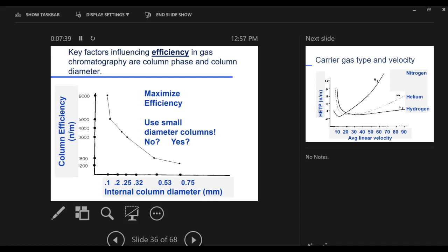Exactly the same column, same packing material, same material. A small column versus a bigger column. And this is our separating ability. The bigger the number here, the more efficient. Basically, if it's going up, it's good. That's what we want. So as it goes down, it's bad. So what's happening? Small diameter columns, very tiny columns, very very efficient. As we go to bigger and bigger columns, bigger diameter columns, our separation power just goes down, down, and down.